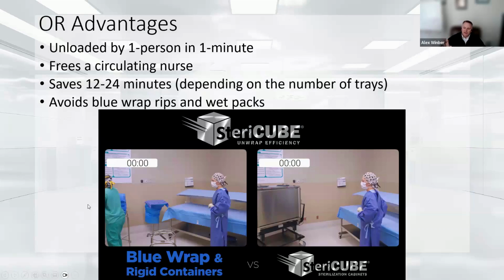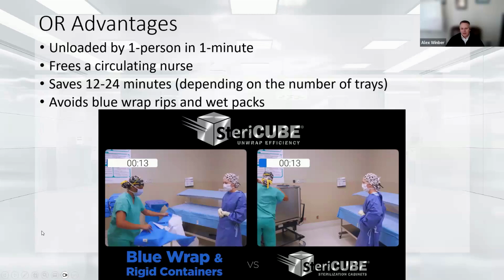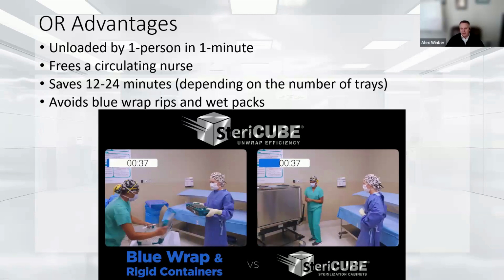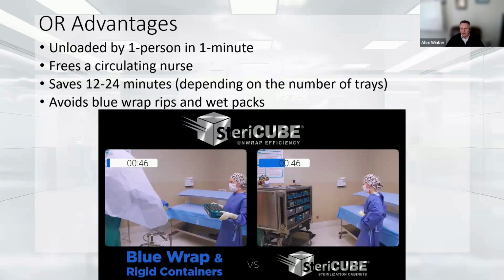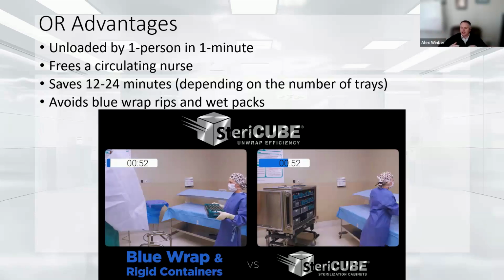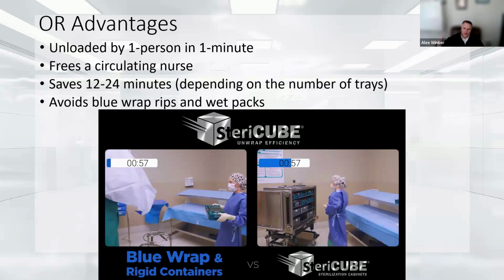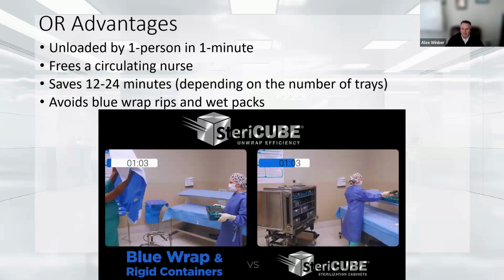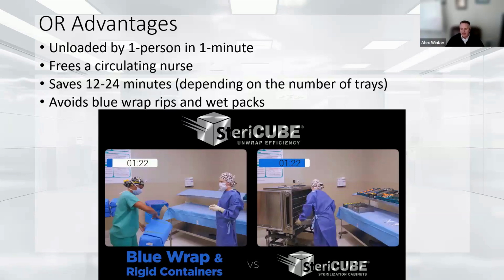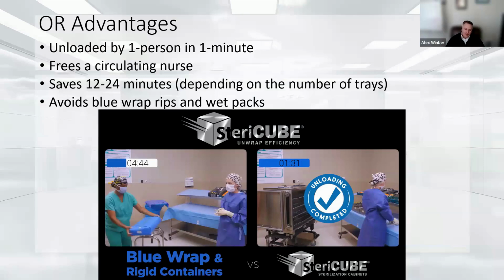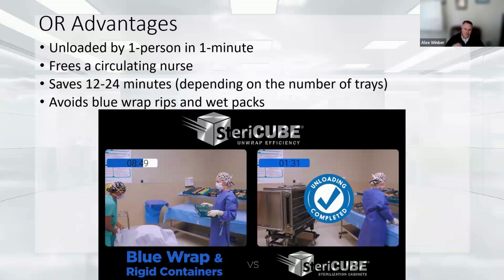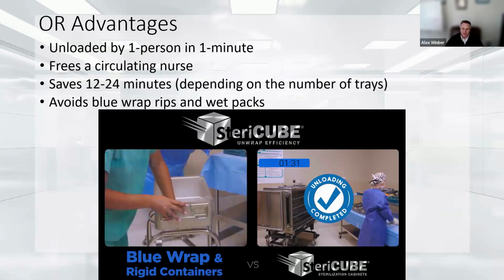So I want to show you these comparison videos between what it's like to use SteriCUBE versus traditional technology. First, you've already seen the video on the left of somebody unloading blue wrap trays and rigid containers. And on the right, you're going to see SteriCUBE. On the right, you see the circulating nurse. They check the filters of the SteriCUBE. They open the door. They push it towards the scrub tech, and then they leave. They go somewhere else in the building to go get the patient or do other things to help the room turn over faster. Meanwhile, the scrub tech can just unload everything in there, and it'll take her about a minute to do that. In the meantime, if you were using rigid containers or blue wrap, you'd still be going through all of this, and it'd be a lot less safe than what you see with the SteriCUBE.